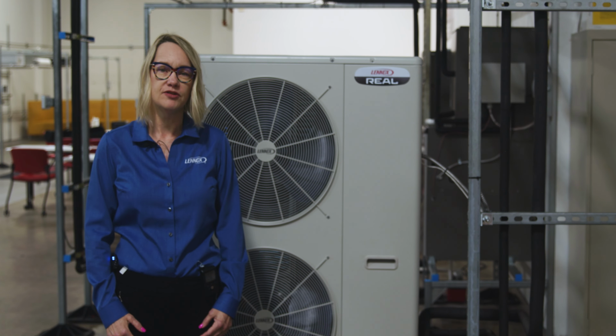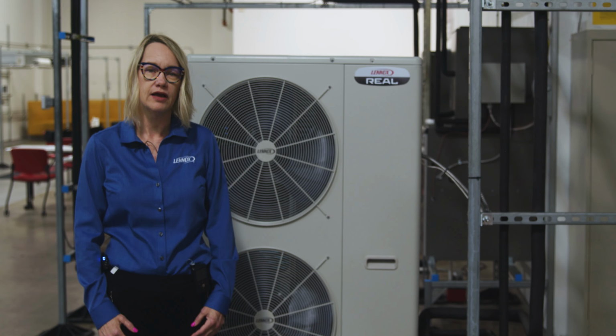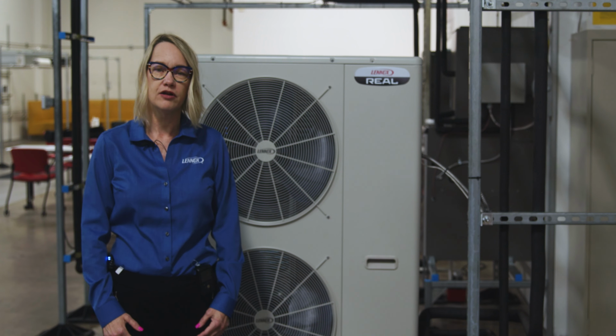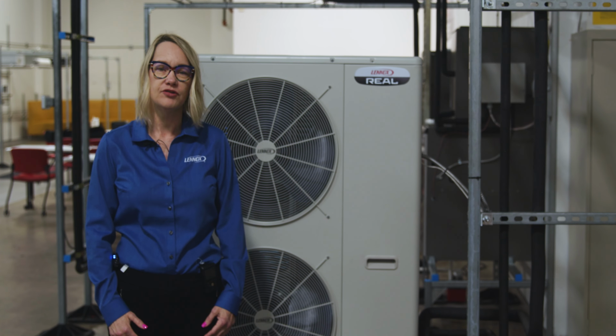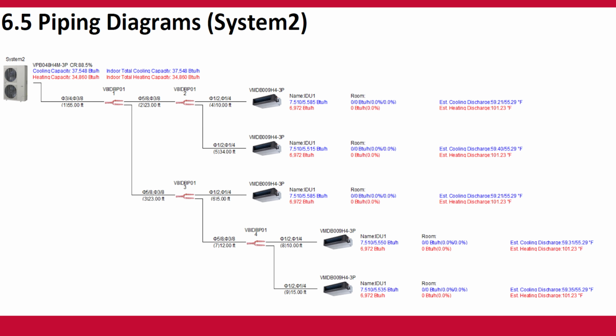One of the first steps in an installation is to decide where to install the indoor units and where to place the condenser, and then measure your pipe runs. The system's piping information will be entered into our software, and then the sizes and lengths will be shown on the system's calculation and selection report. Notify your Lennox representative of your initial pipe measurements and be sure to keep them informed of any pipe changes as they occur.